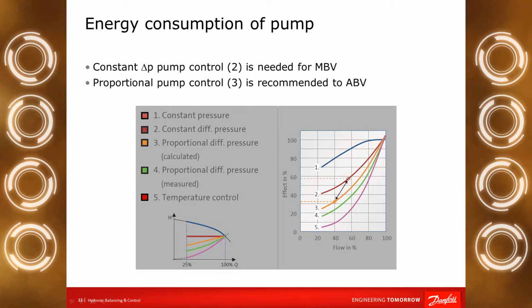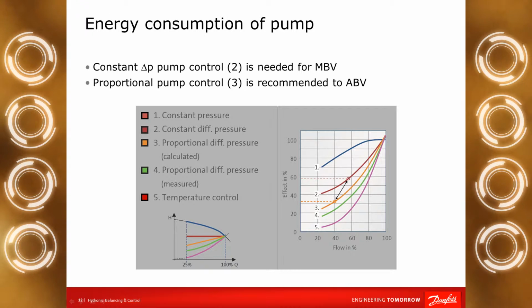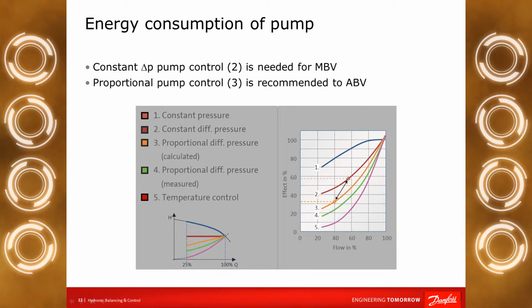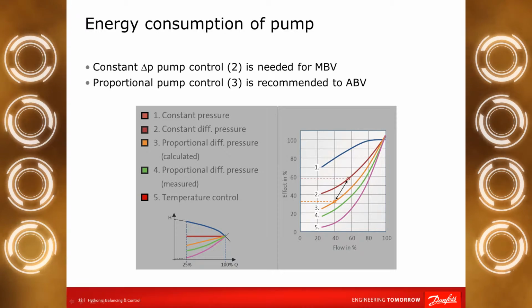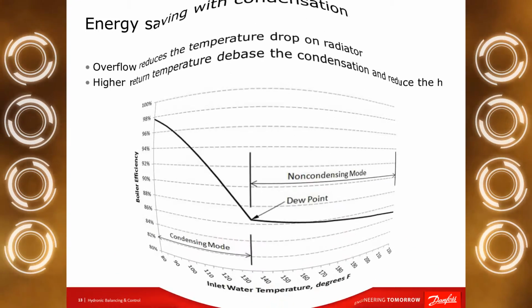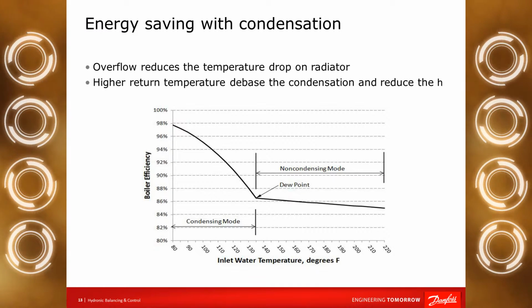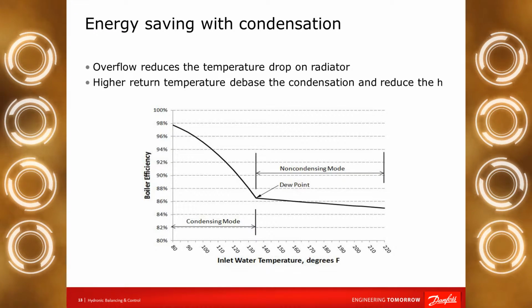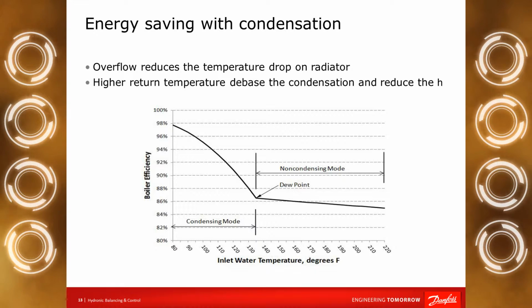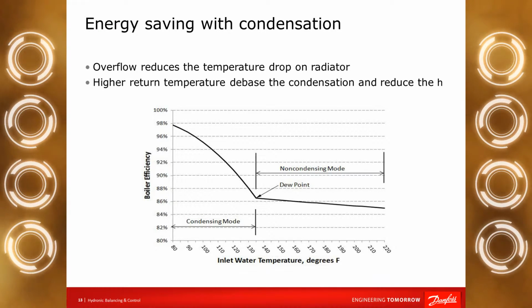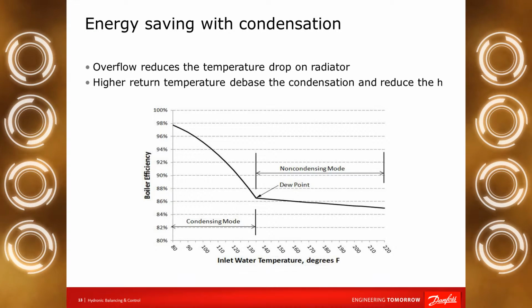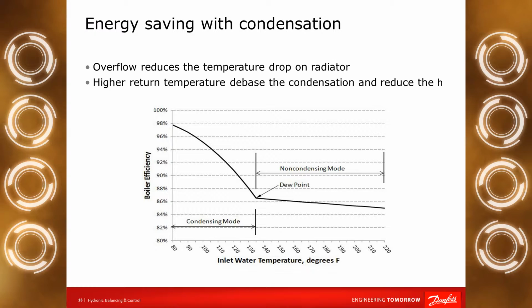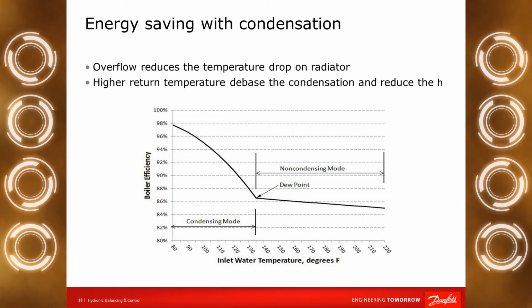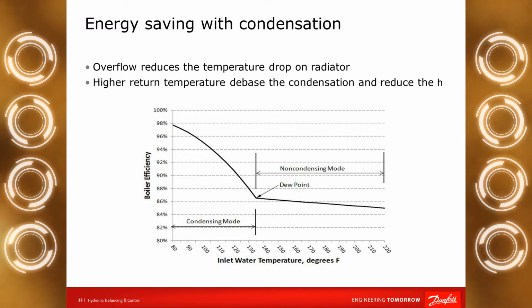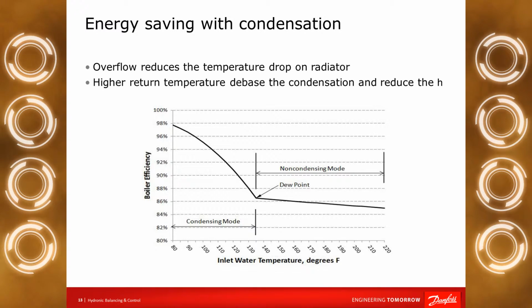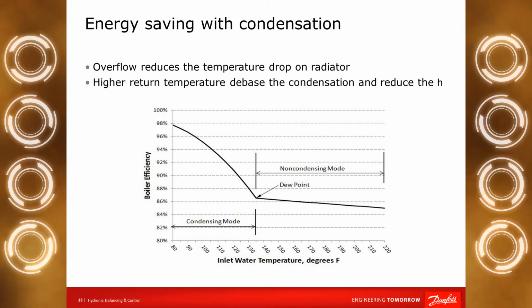If we take into consideration these 2 effects, we can see clearly how much more energy we use with manual balancing valve with constant delta P control pump. The next effect is the saving on the boiler, for example, if you're talking about the boiler system. Especially if you use a condensation boiler, it's very, very sensitive about the return temperature. You can see on this chart how the efficiency of the boiler changes based on the return temperature. As I mentioned, we have overflow in the system, smaller delta T, higher return temperature, lower boiler energy efficiency.